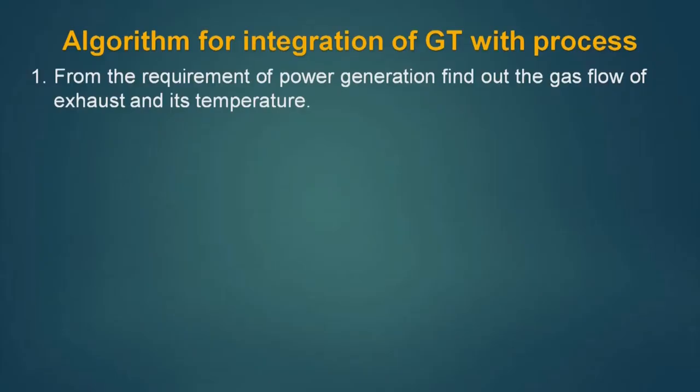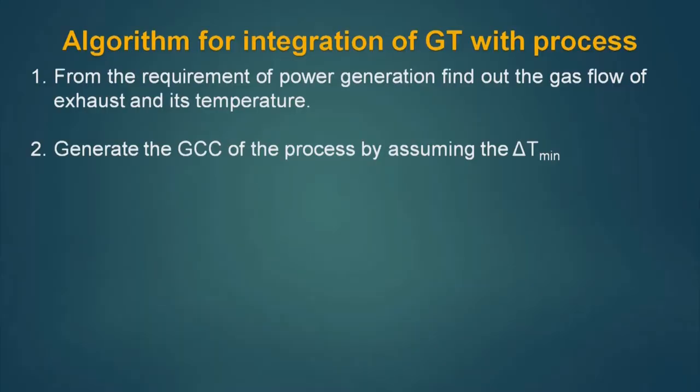Let us now formulate an algorithm for integration of gas turbine exhaust with a process. Point number one: from the requirement of power generation, find out the gas flow of the exhaust and its temperature. Second, generate the GCC of the process by assuming a delta T minimum value. This delta T minimum value is an ad hoc value which can further be optimized through economic analysis.